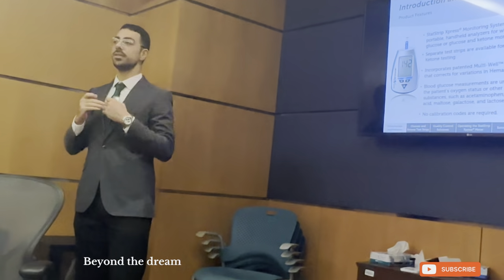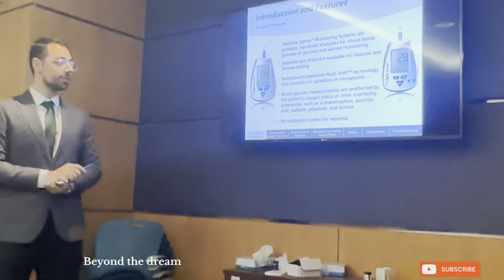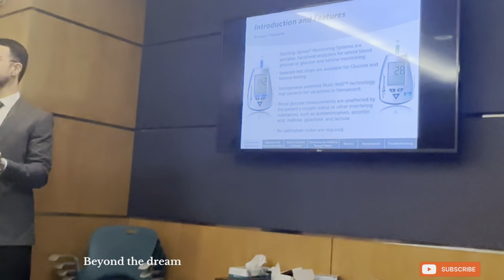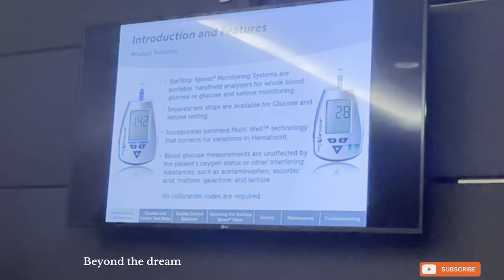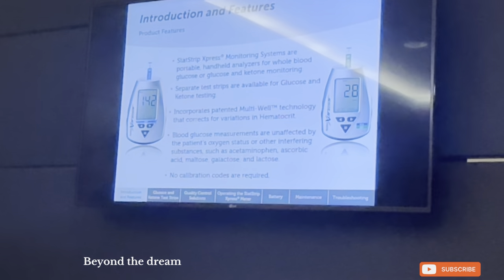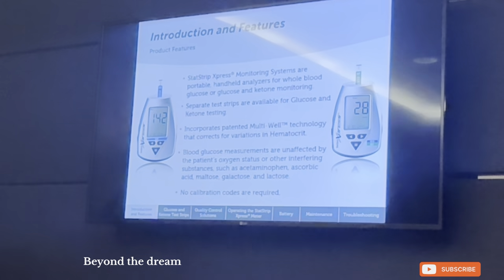The reason why Al-Muasah chose us as a company for glucometers and ketones is because our technology is the only patented technology that erases, removes, or bypasses all interferences — or at least most interferences. Both glucometers are unaffected by the patient's oxygen status and other interfering substances such as acetaminophen, ascorbic acid, maltose, or galactose. All of these can have an effect on glucose outcomes on all glucometers, except for the StatStrip Xpress.